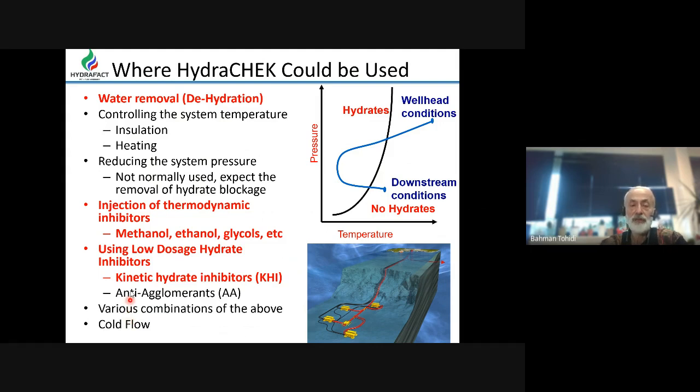So far, we have tested and we see that the concept of HydraCHEK can be used with thermodynamic inhibitor, kinetic hydrate inhibitor, and also dehydration. So for these applications, we can design the HydraCHEK to be used for controlling hydrate, to determine where the hydrate phase boundary is.